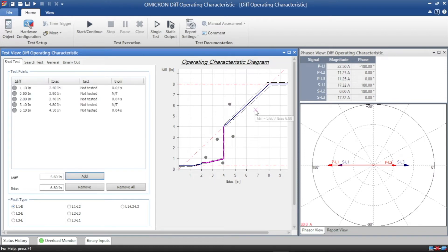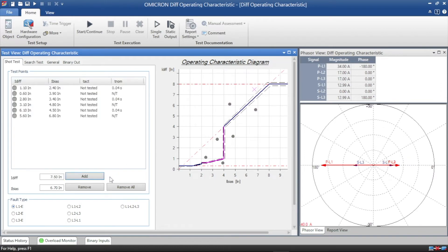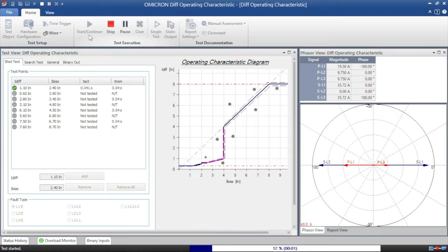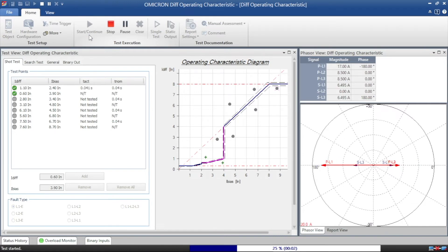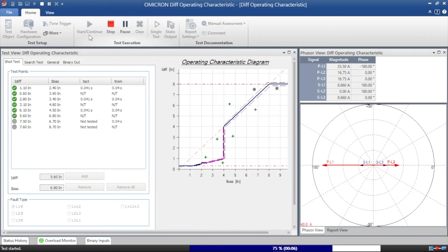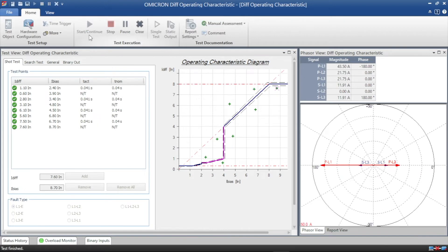We can choose each value for tripping and non-tripping regions. And we can run the test and check whether trip or not. Now we can choose each value for the tripping region. Yeah, see here the first value tripped by 0.04 seconds.